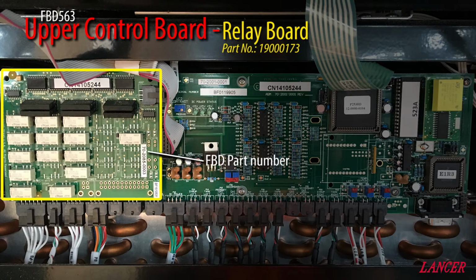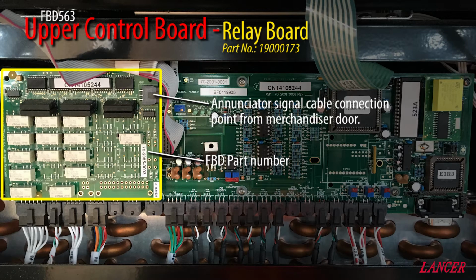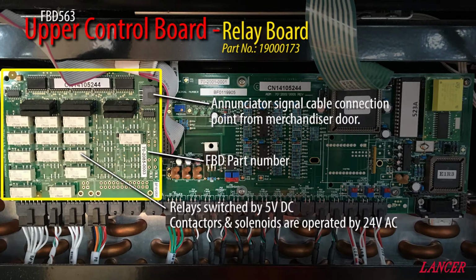The relay board is common to both FBD 562 and 563 units. It is mounted to the upper control board by plugs and sockets on the reverse side of the relay board. Please note the location of the FBD part number. This is the reference for setting up a new revision of the upper control board. The merchandiser door annunciator panel signal cable is connected to the socket on the top right hand side of the relay board. It is important to note that the relay coils operate on 5 volt DC and that these are typically switching 24 volts AC.